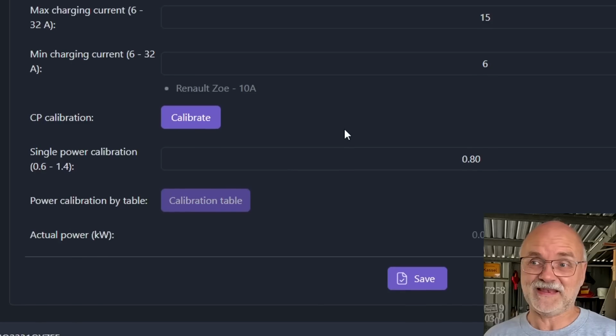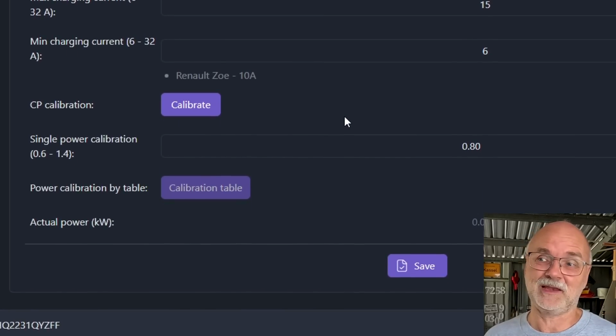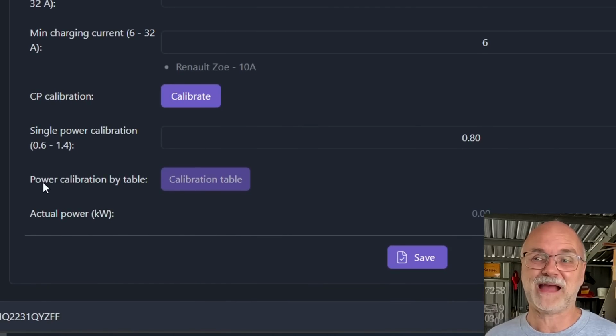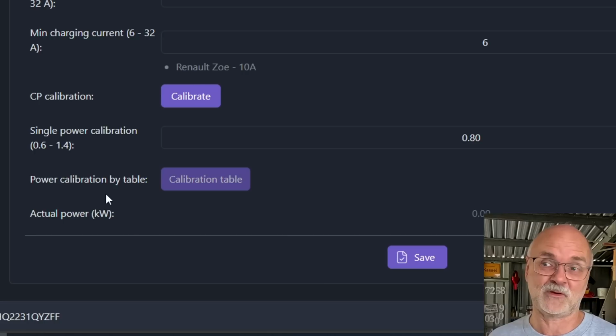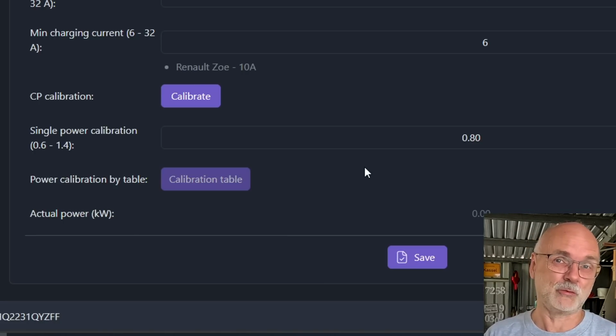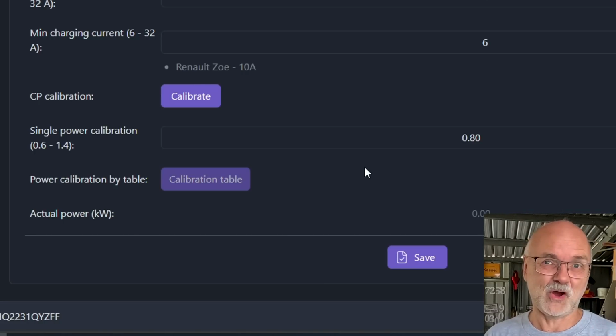You can select either a single power calibration value here, or use a power calibration table - a brand new feature that wasn't in the 1.3 firmware version. The only thing the station actually knows is the current going into the vehicle; it knows neither the voltage at the port output nor the power factor of your vehicle, so it's impossible to show accurate charging power without all those details.